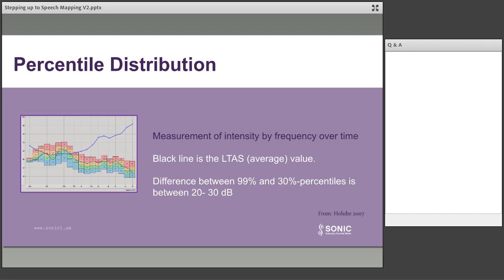But we know that speech has dynamics, about 20 to 30 dB in dynamic range. And so even though, say, at 1K you'll have the output line at a particular level, we know that there will be parts of speech that will be louder than that, and they're the orange and red bits, and then parts of speech at that frequency that will be softer. There will be a range, and this is a visual representation of the variation at each frequency over time of a 65 dB input speech. So it can be very useful, and I am going to come and talk about that a little bit later in the presentation as well.